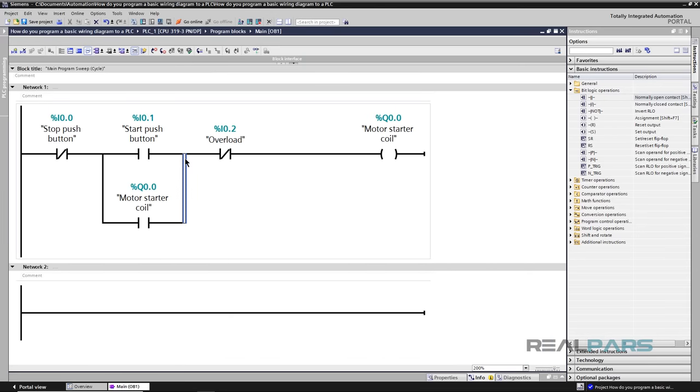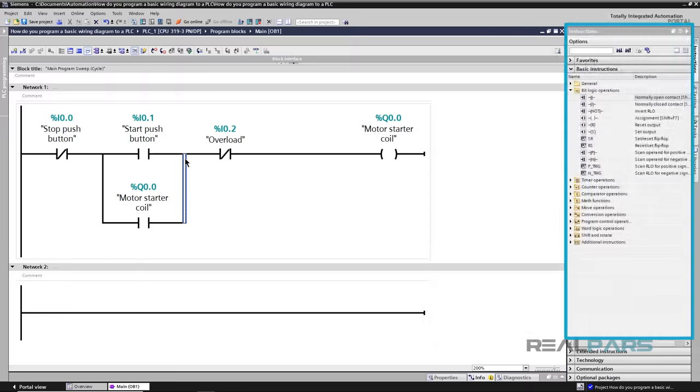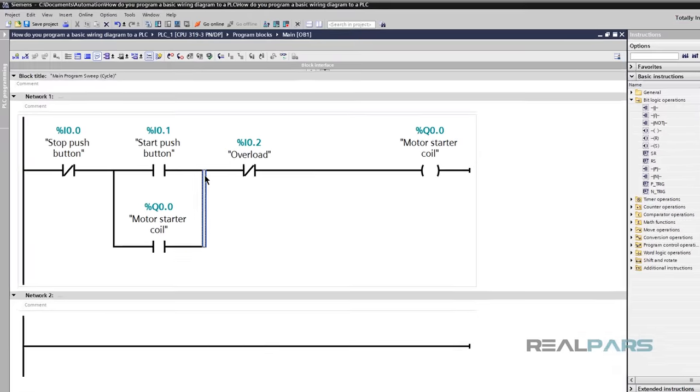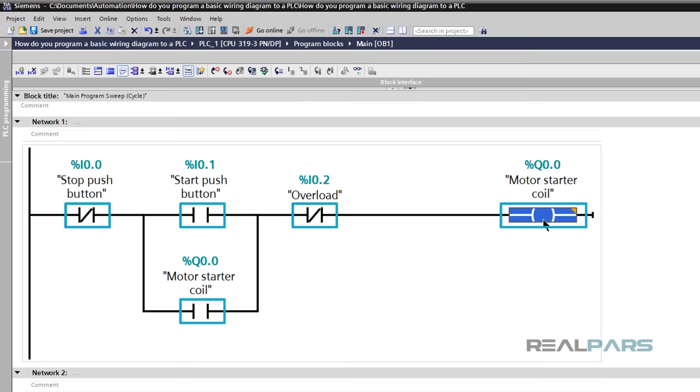Let's look back at what we've learned. To program a simple motor start-stop circuit, we need to read the electrical diagram from left to right and use our toolbox on the programming software. You will be using the most common bits: examine on, which will represent a normally open contact, examine off, which will represent a normally closed contact, and output coil or output energize. Again, the language is sometimes different between manufacturers, but the symbols pretty well look the same.